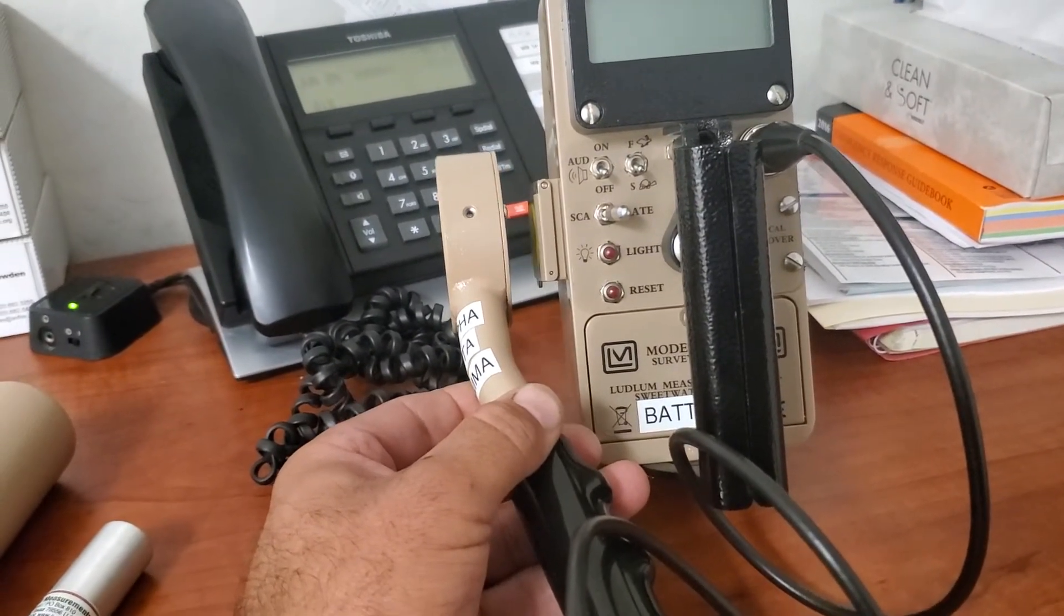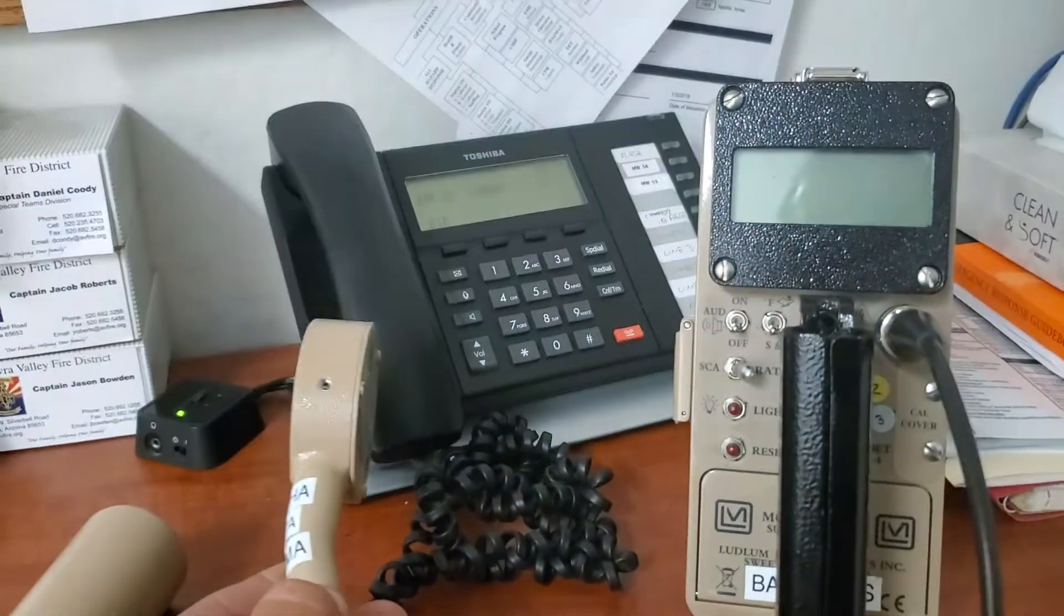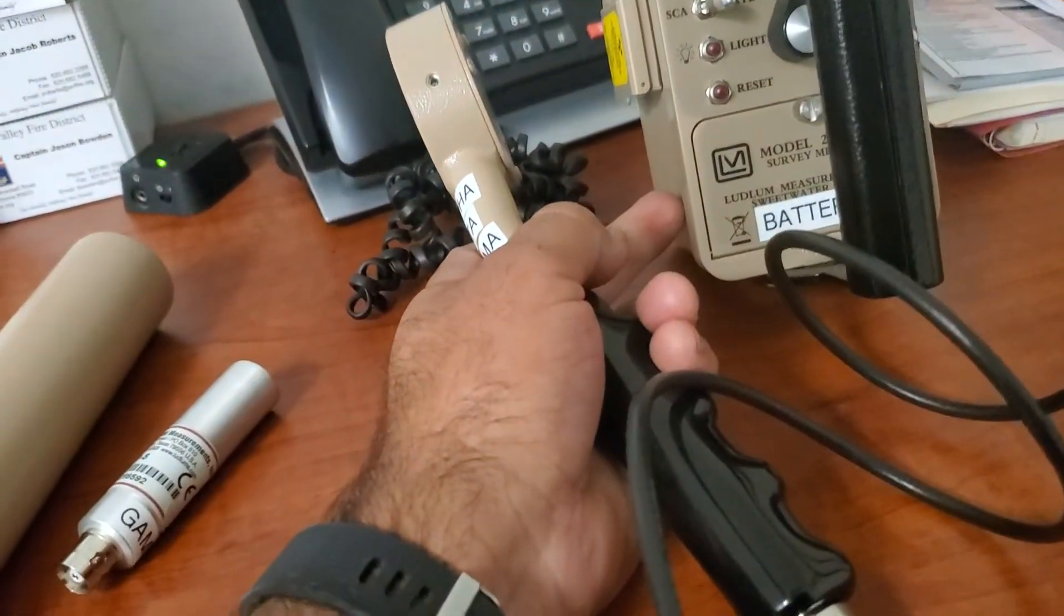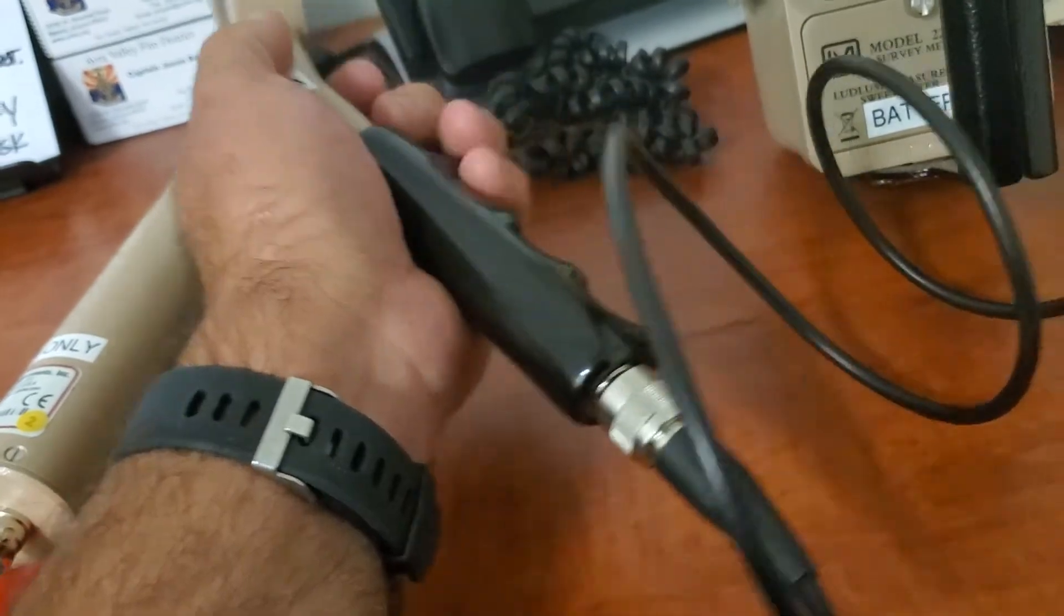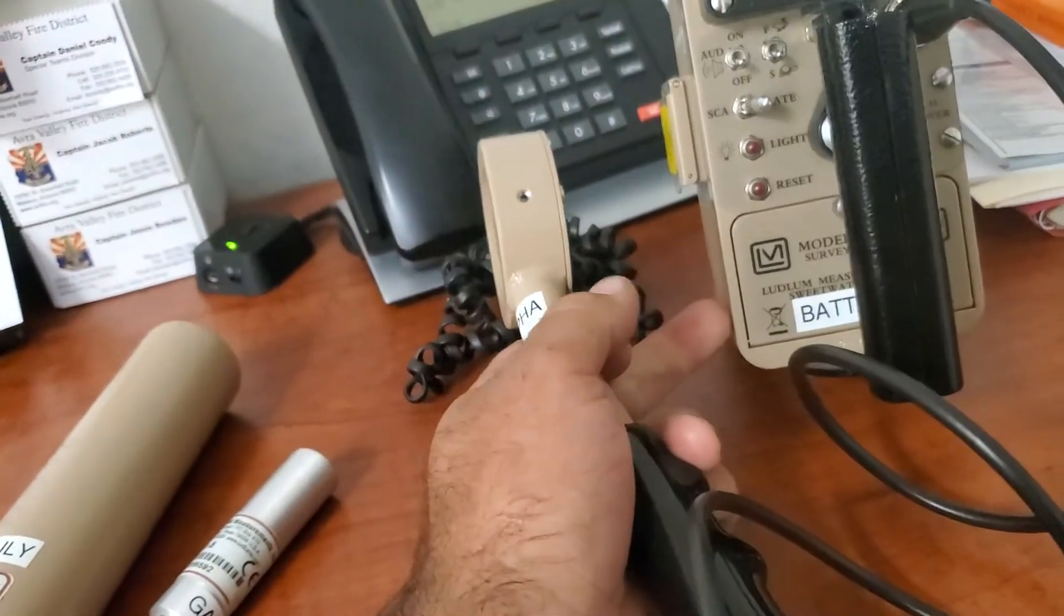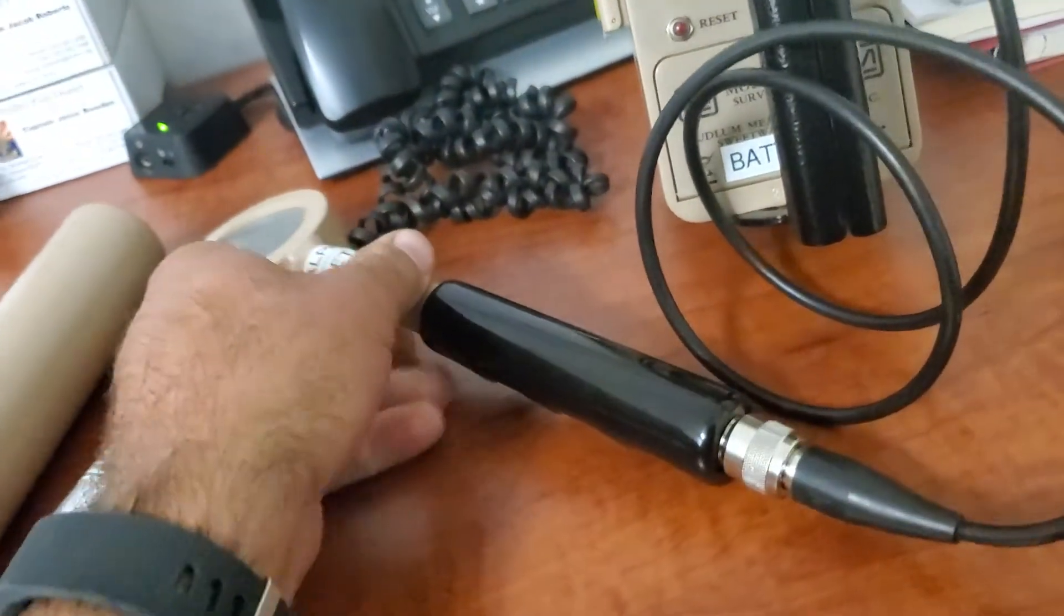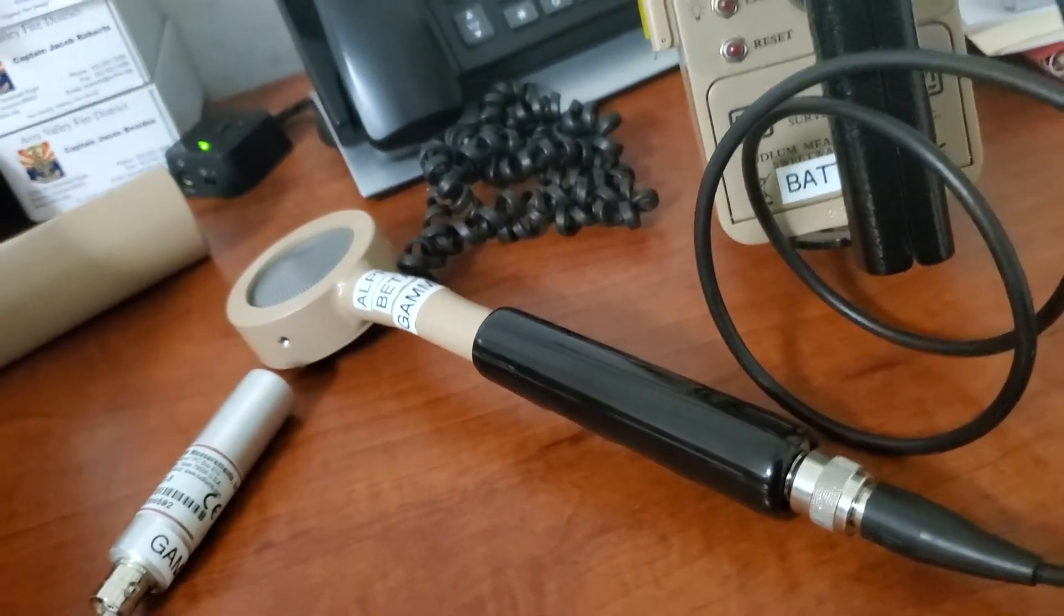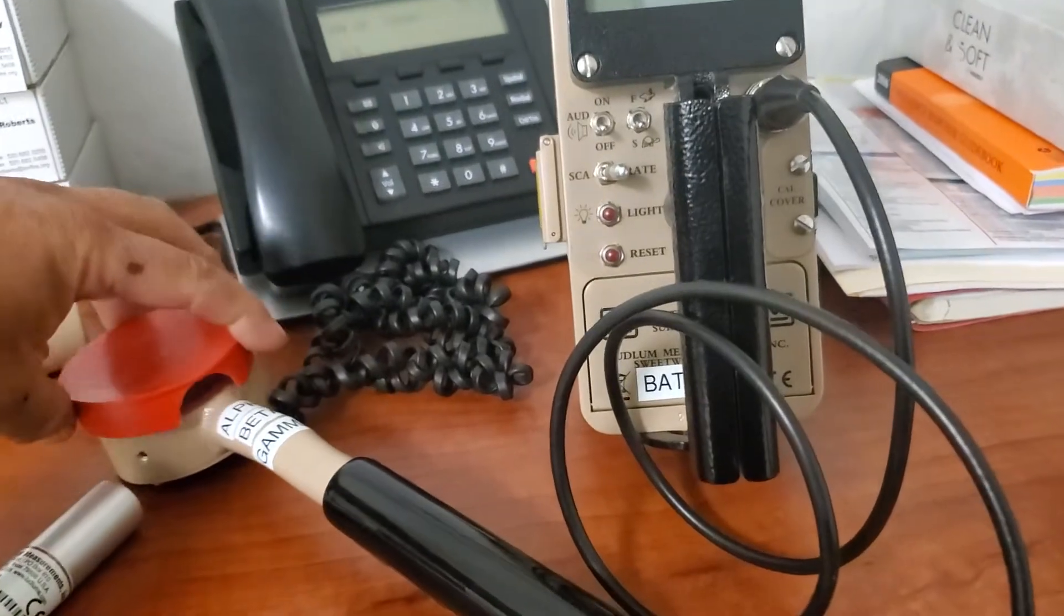If you want to determine if you had beta radiation, you're going to move out to the beta past the alpha into the beta range and meter that way. Gamma radiation is the same way, you're going to move way far away and gamma radiation is going to go through the back of this at a far distance. So that's a good way to kind of break apart what you think you're dealing with: alpha, beta or gamma.